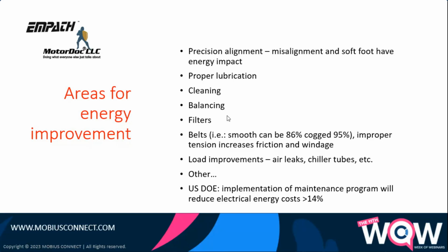I mean, the 50% reduction in energy we had at NIH was primarily cleaning chiller tubes. And then US DOE, they say 14%. To be perfectly blunt, 14% is a minimum. We're normally seeing much, much higher. The amount of waste we have from not properly maintaining machines is incredible.